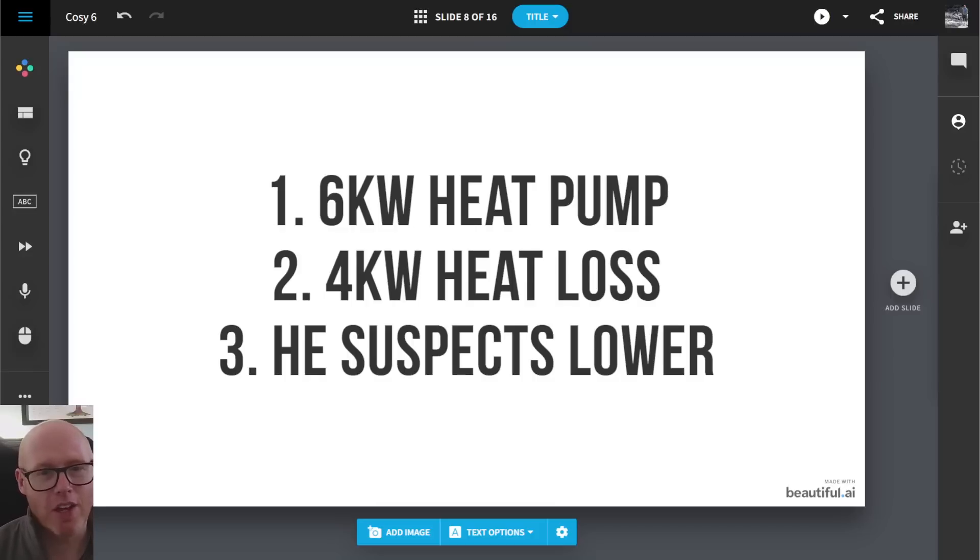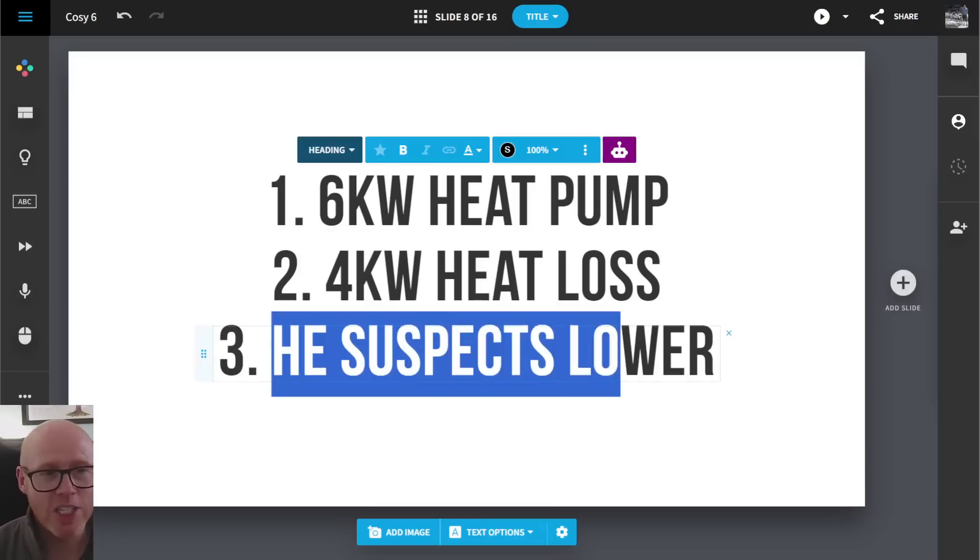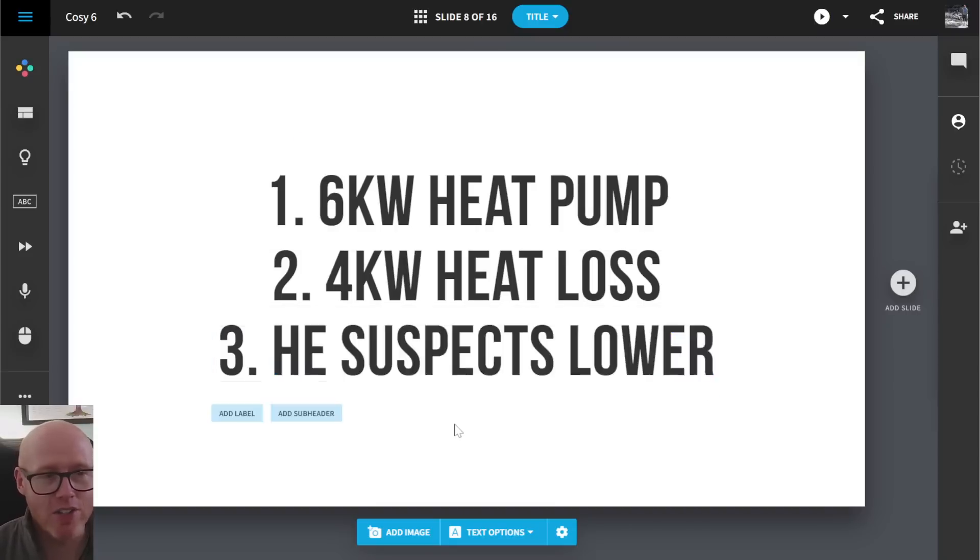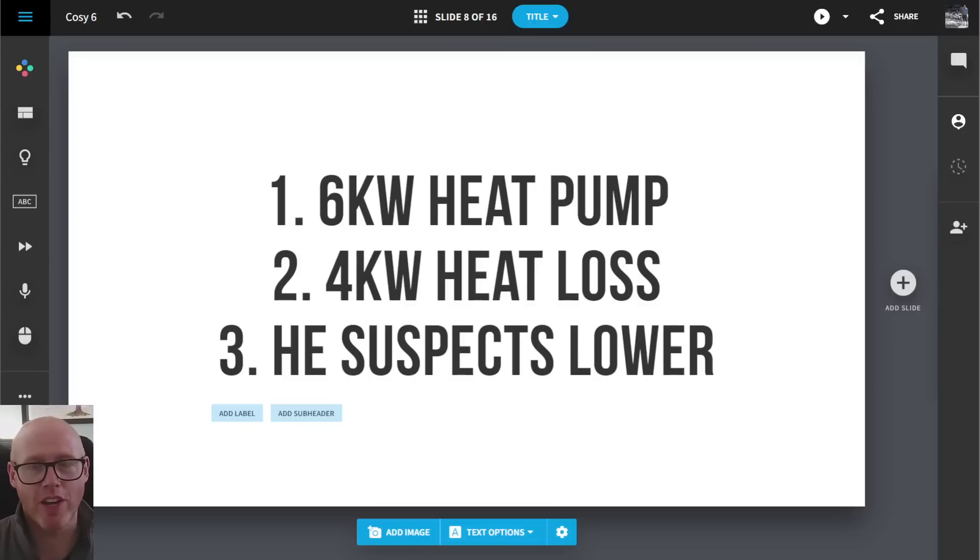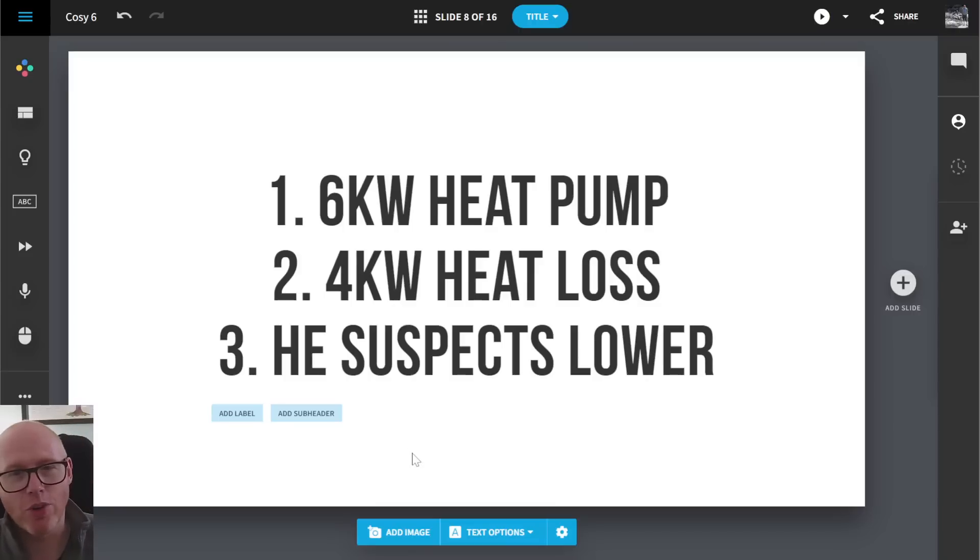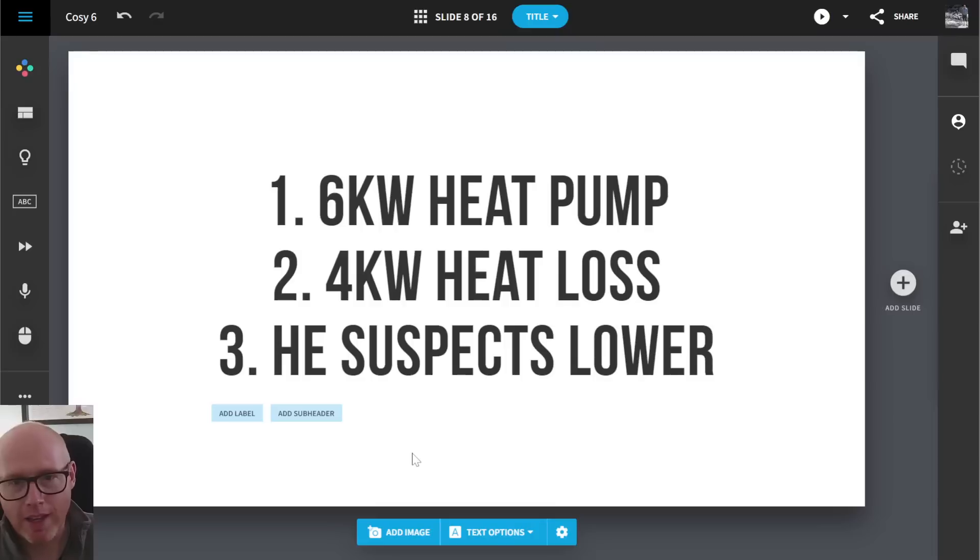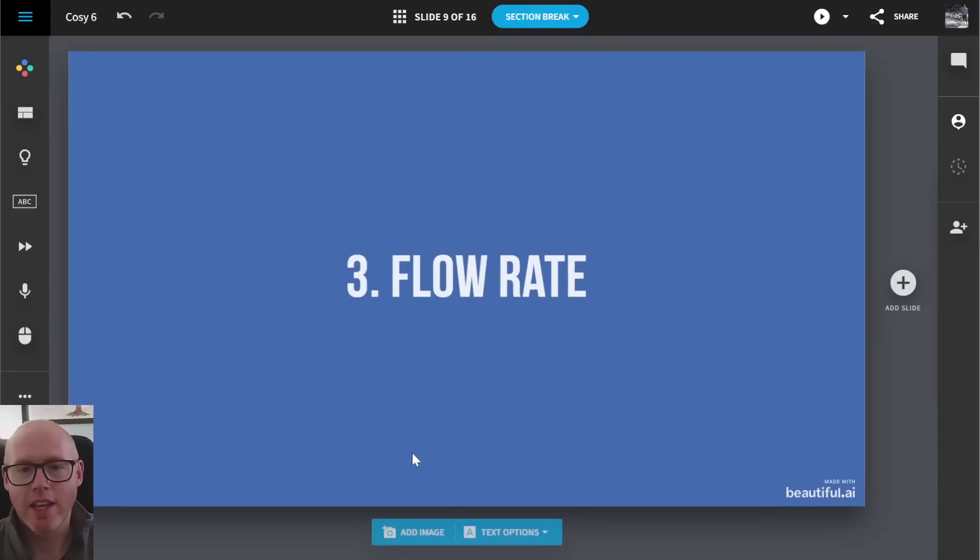So we suspect that the heat pump will modulate down to two kilowatts. And most of the heating season, he won't need two kilowatts if his house is four kilowatts in the worst conditions. He suspects his heat loss is even lower. And it doesn't take a lot in terms of air change rates to bring that heat loss calculation down to maybe three kilowatts to knock 10, 15, 20, 25, 30 percent off a heat loss calculation. So that would be interesting to know. And I'm sure Octopus must have ways from their monitoring system to use a dynamic measurement to dynamically calculate the heat loss calculation.